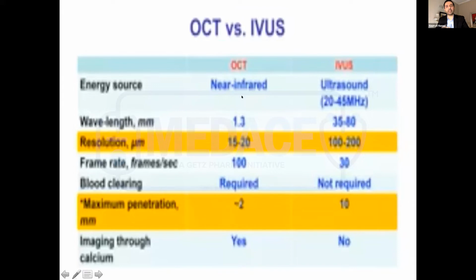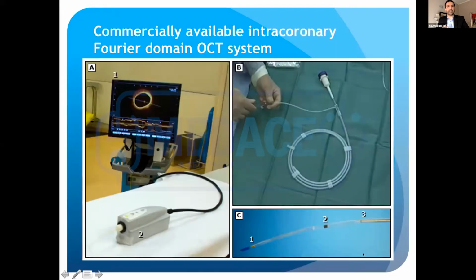So comparison with IVUS, it's near infrared technology. Wavelength is around 1.3 millimeters, was 35 to 80 millimeters over here. Resolution is 15 micrometers. It's 100 micrometers over here. And maximum penetration is 2 millimeters on each side of the catheter. It's 10 millimeters over here. And you can image through calcium with OCT, which you can't through IVUS because of the acoustic shadowing that happens. This is what the OCT catheter looks like. Similar to the system that is with IVUS, unless you have it integrated in the lab. And this is where you plug in the catheter, and this is the light source area and where you get the images as well.